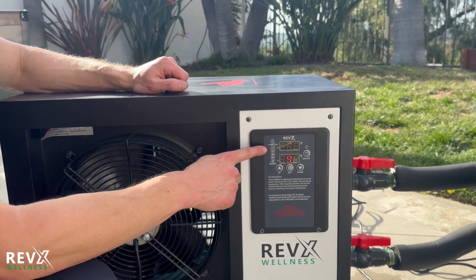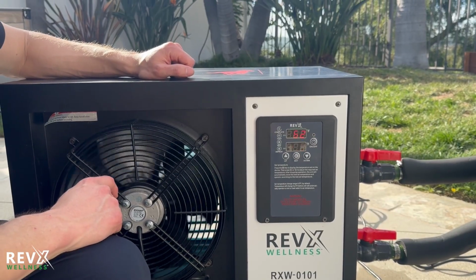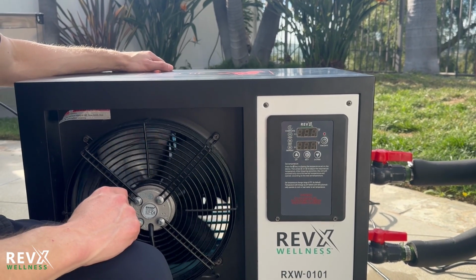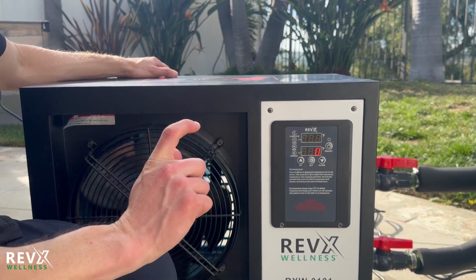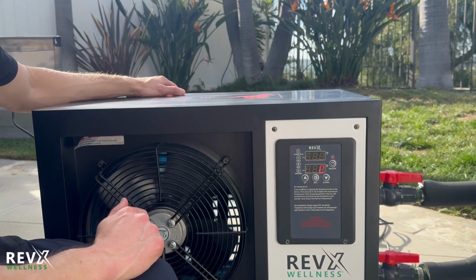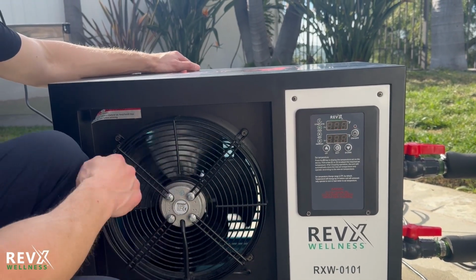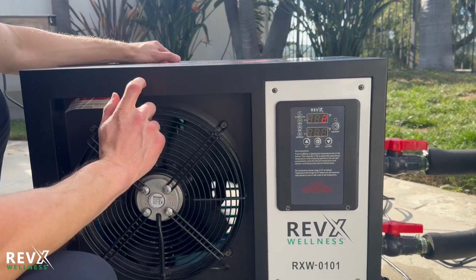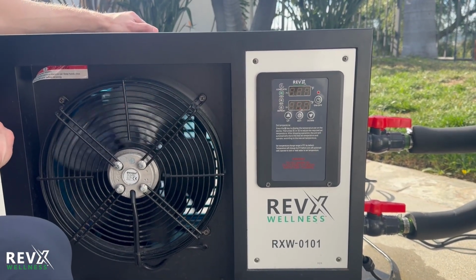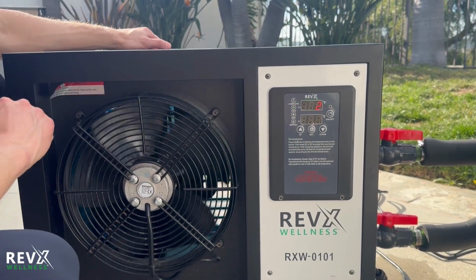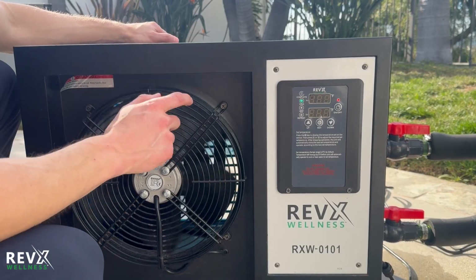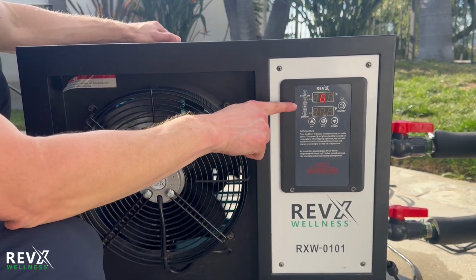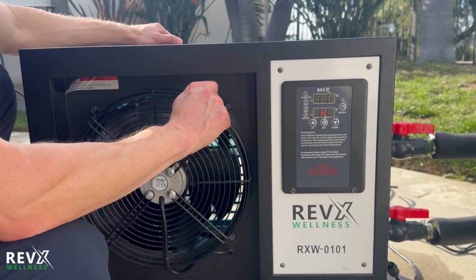Okay. All right, so the fan just kicked in. The light will stop blinking and become solid in a couple seconds here, and you will hear the compressor kick in. And when the compressor kicks in, it will be just a humming noise, no rattling, nothing. There you go. The compressor just kicked in. The light is now solidly illuminated. So this is as loud as the system will ever get. So this is cooling mode. Once the cooling mode is complete and the temperature is 40, the complete light will be illuminated.